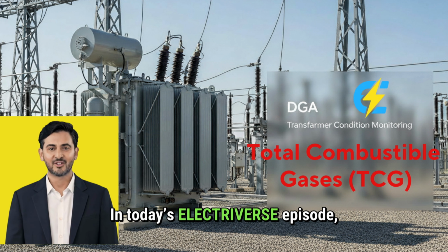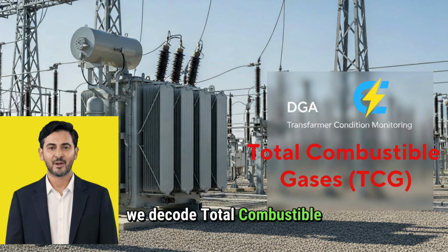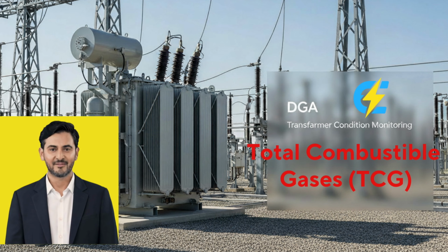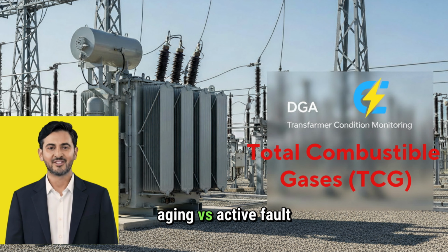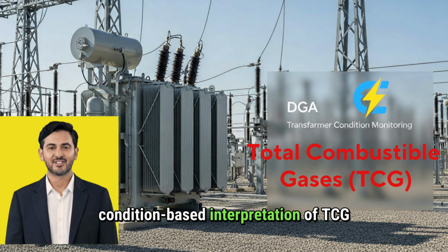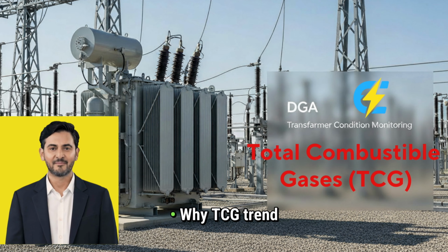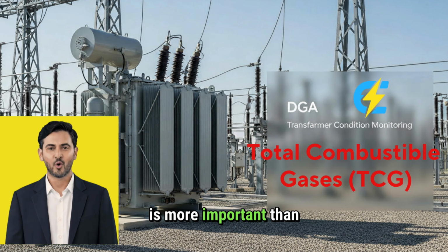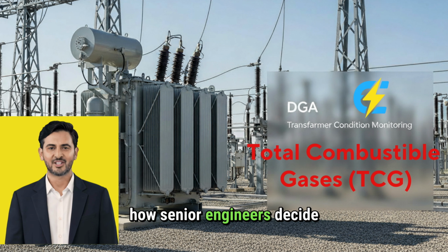In today's Electriverse episode, we decode total combustible gas, TCG. What gases are included in TCG? Why TCG is used as the first screening tool. Difference between slow aging versus active fault. Using TCG, IEEE condition-based interpretation of TCG. Why TCG trend is more important than absolute value. And how senior engineers decide urgency using TCG.